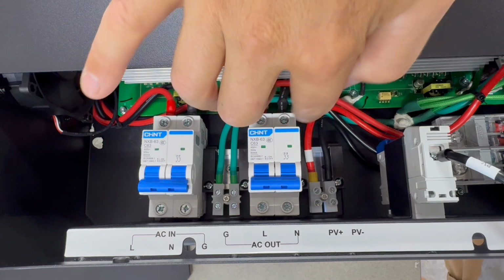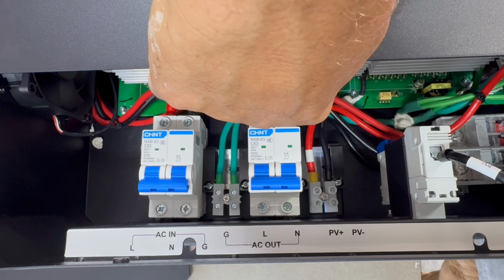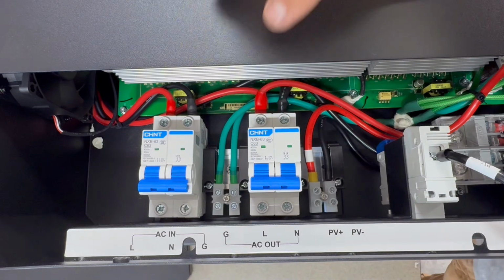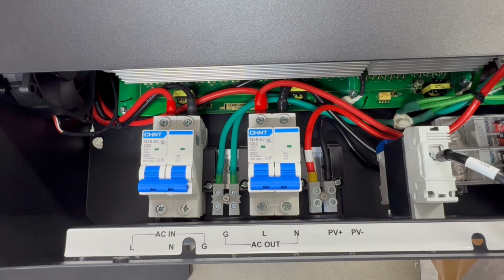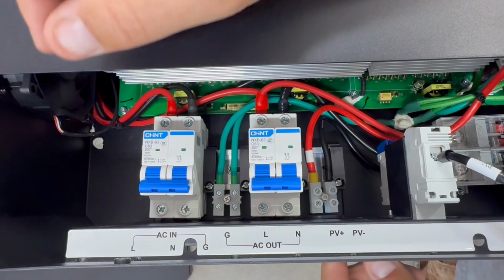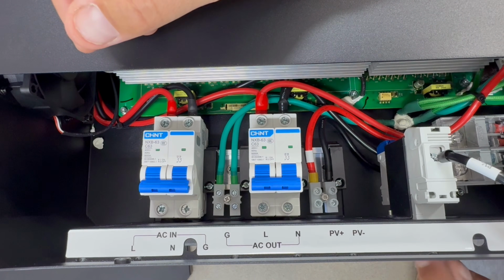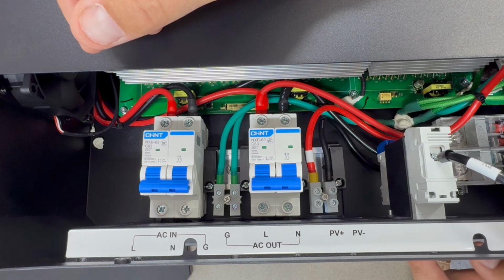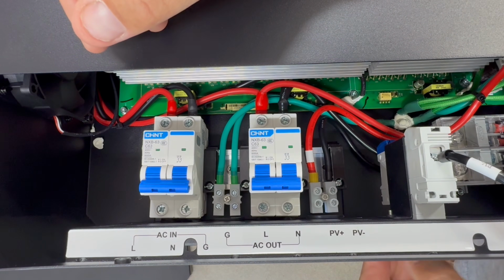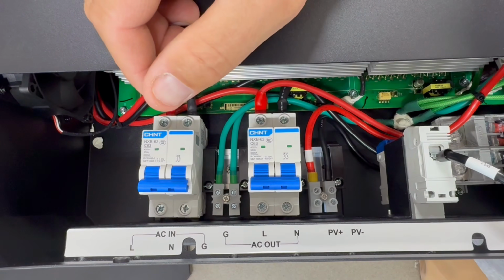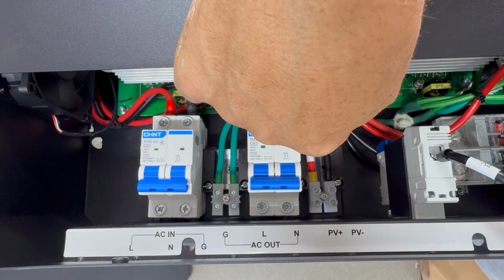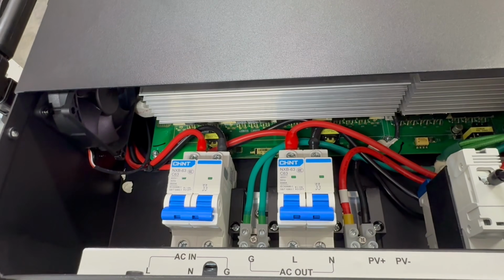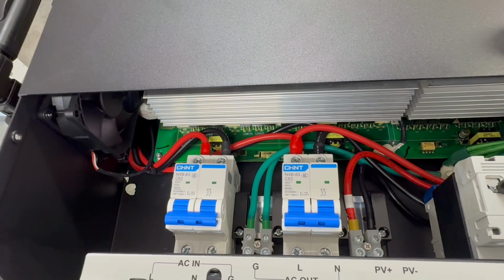And coming off the PV here, we have 105 degrees Celsius 11 gauge wire. Yeah, it says 11 gauge wire. That's a bit odd. My guess is, with the specs they had on the PV, they're probably just talking about the circuit breaker for the PV itself being 50 amp rated. Not sure what's going on there, but you've only got 11 gauge wire once you get into the unit.